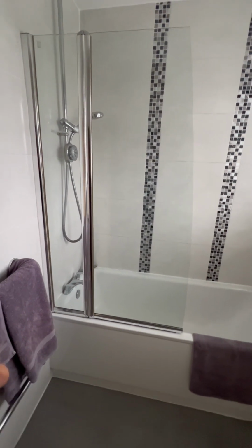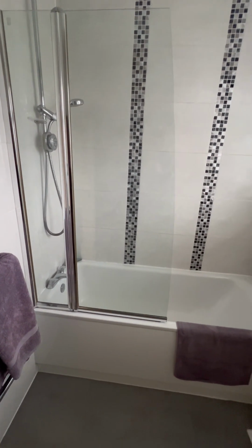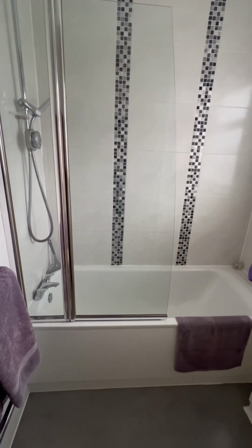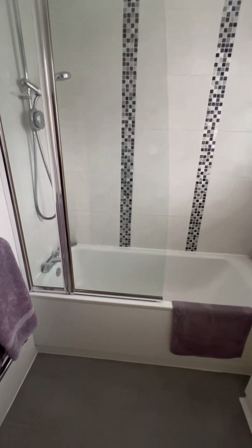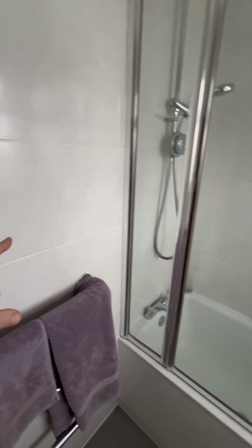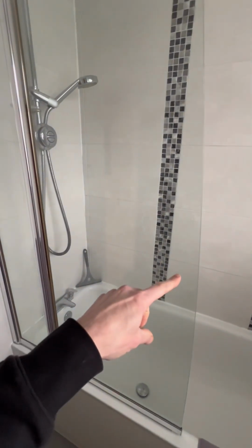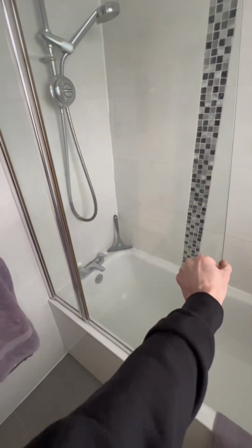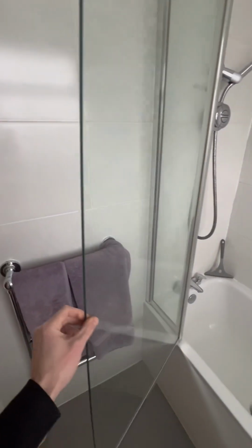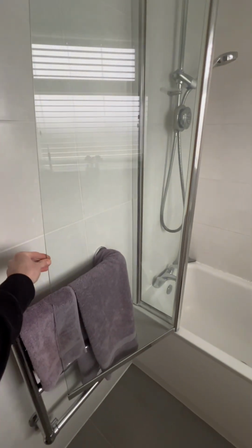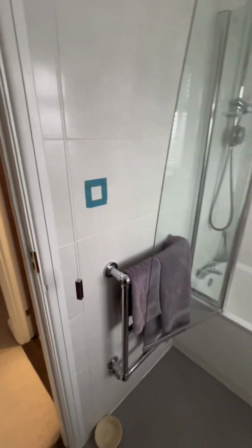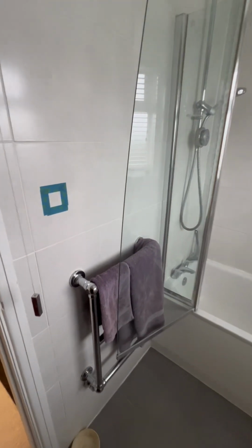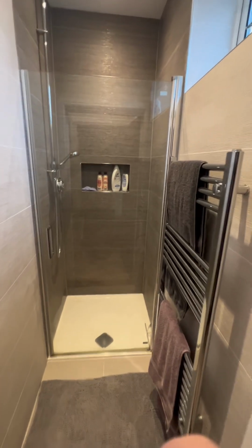So we'll take this bathroom as an example. We have a standard bath here with an opening glass door. Using our 60 centimetre rule basically off the edge of the bath and also with the door opening, as long as there's anything outside of that, you can have the switch there. Thankfully this door is actually 600 wide, so when I open it here, it basically creates our zone for us. So if I pull it open, gets us up to the 600 mark. So anything beyond that glass panel basically, we can have electrical connections in there, switches, etc. There's also no issue to having towel rail isolators or underfloor heating isolators in that area either.